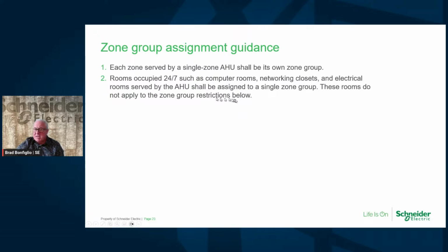Okay, they could set up different restrictions depending on what you have to do. Again, you'll have to look at the facility to see. Hopefully, if it was in the design, computer rooms and network closets might actually have a dedicated unit for them, like a VRF or a DX unit that serves that area. That way, you don't have to try to group it into the zone with the air handler. But again, it depends on design.